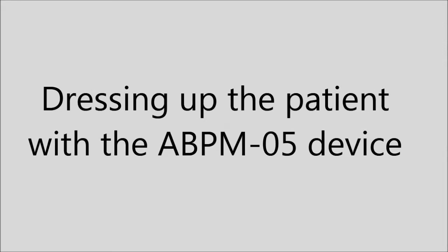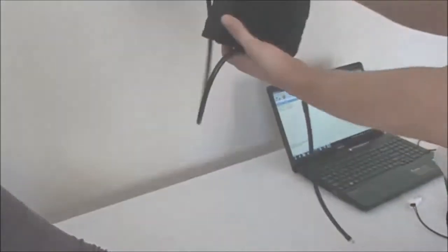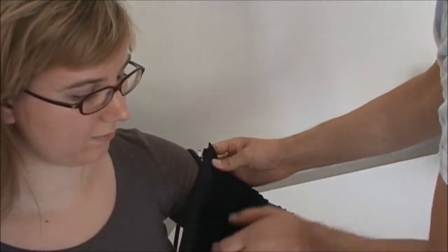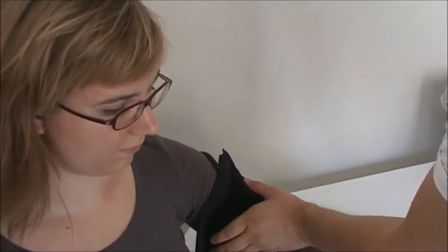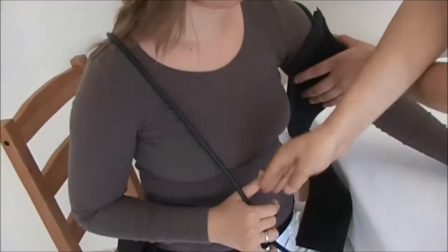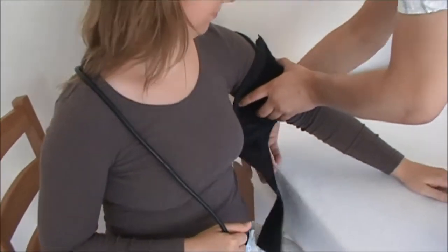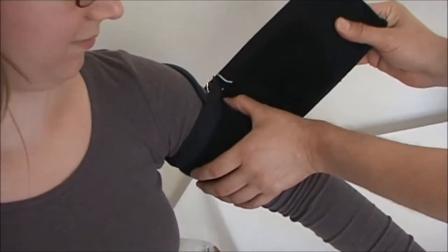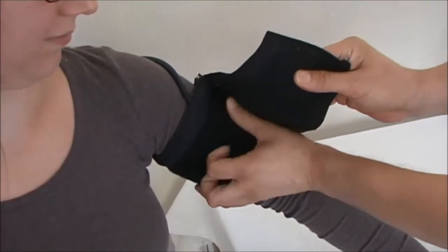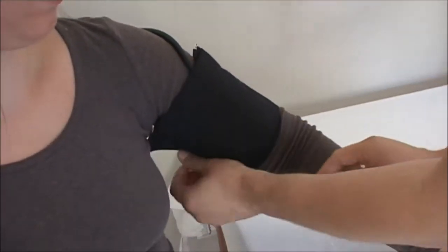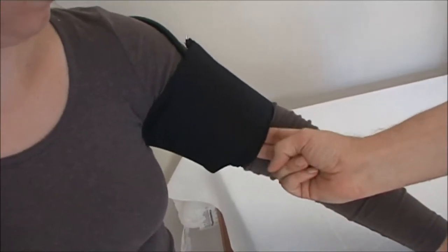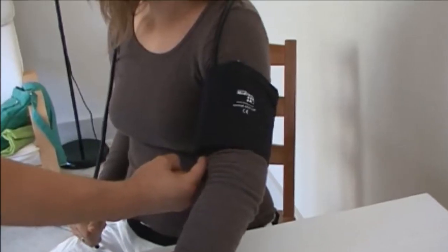Proper fitting of the cuff is paramount for successful measurement. It is advisable to wear a thin shirt or blouse under the cuff. It is recommended that the cuff be applied as tightly as acceptable for the patient. A too loose cuff will cause much longer blood pressure measurement times and possibly aborted measurements.